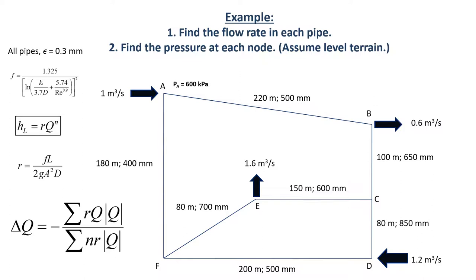I handed out this paper because I'd like you to sketch your initial flow balance on paper and work with someone else — don't just do this individually. It's so easy to get the initial flow balance wrong, and then the problem will never converge. If your initial flow balance does not have in equal out at each of the junctions, then it doesn't matter how many iterations you do — the problem will never conclude successfully.